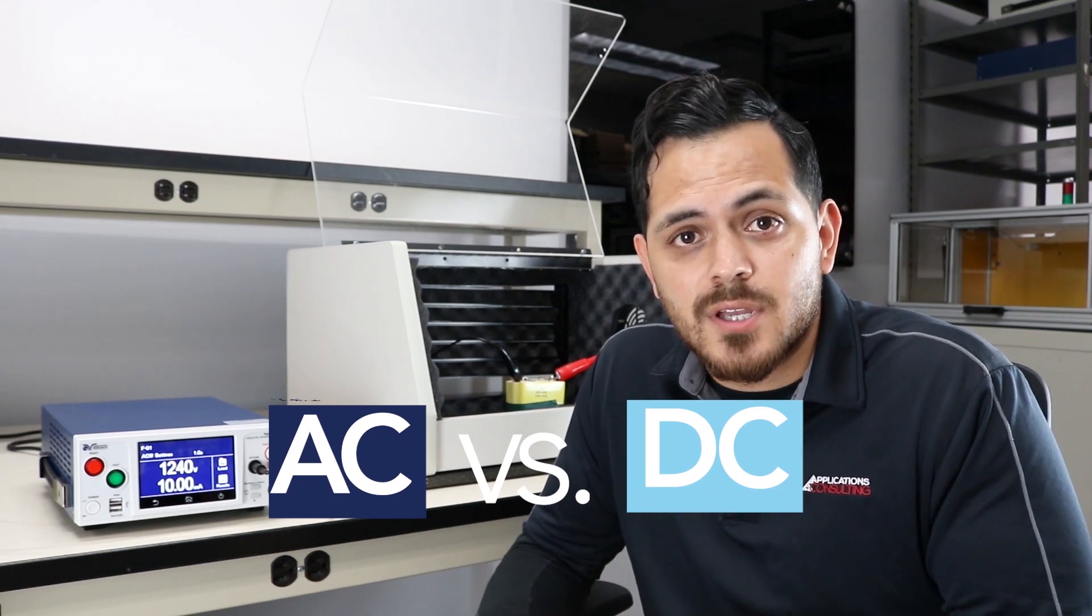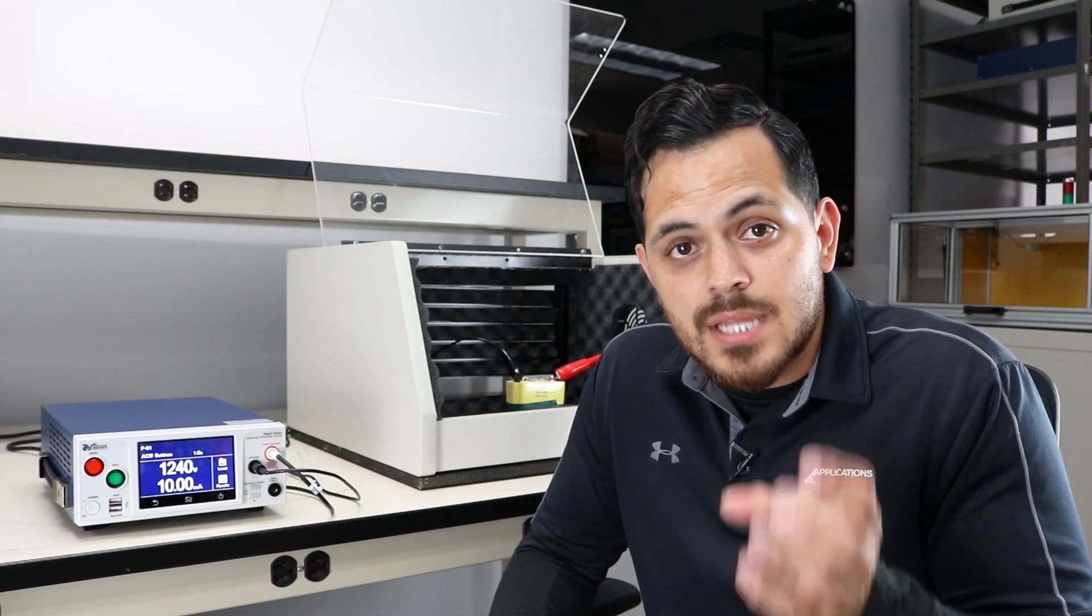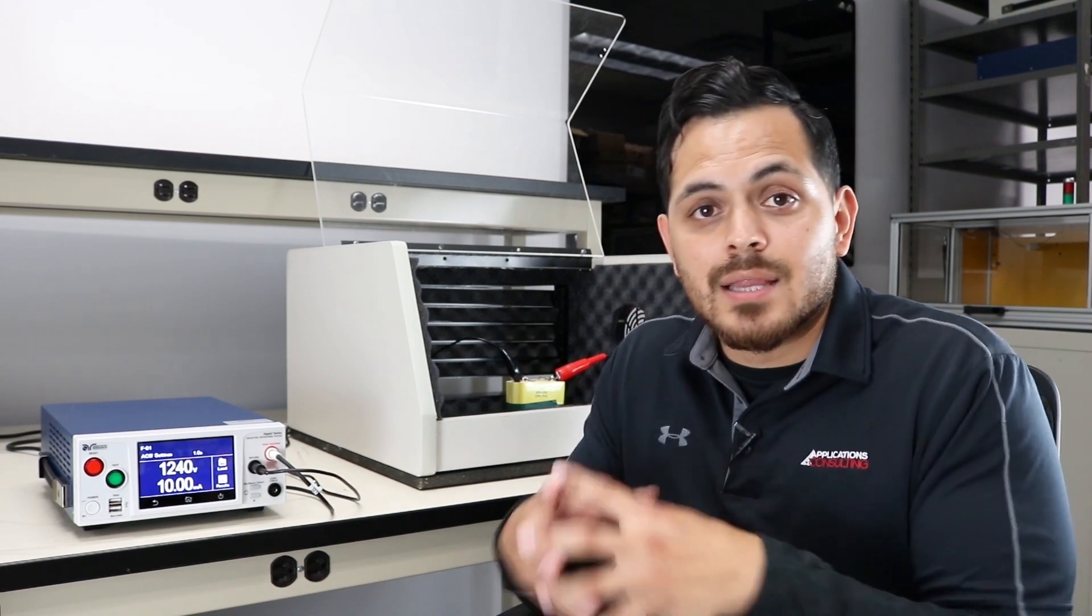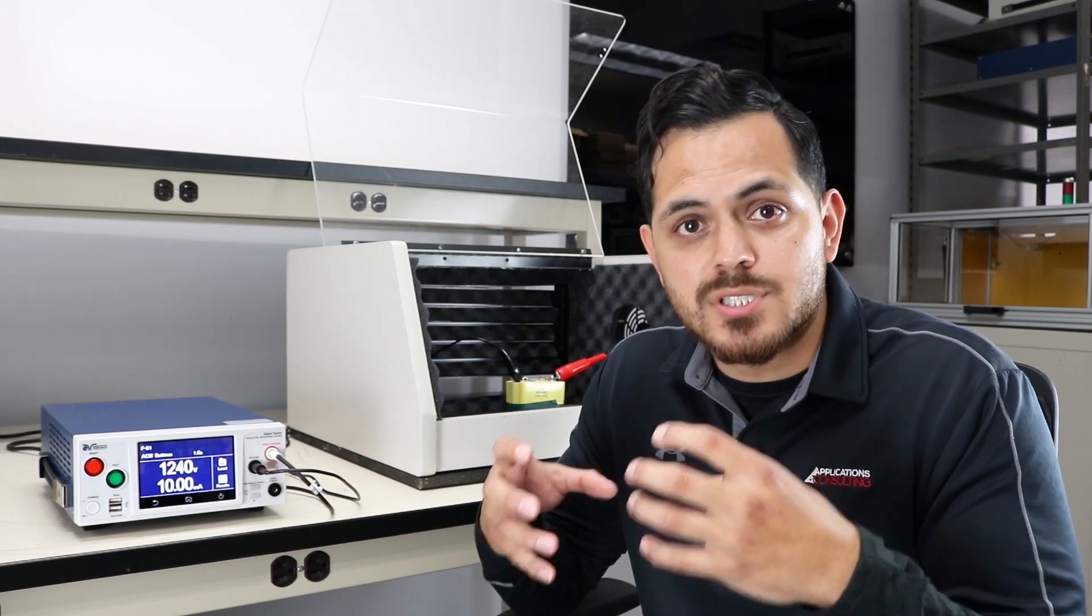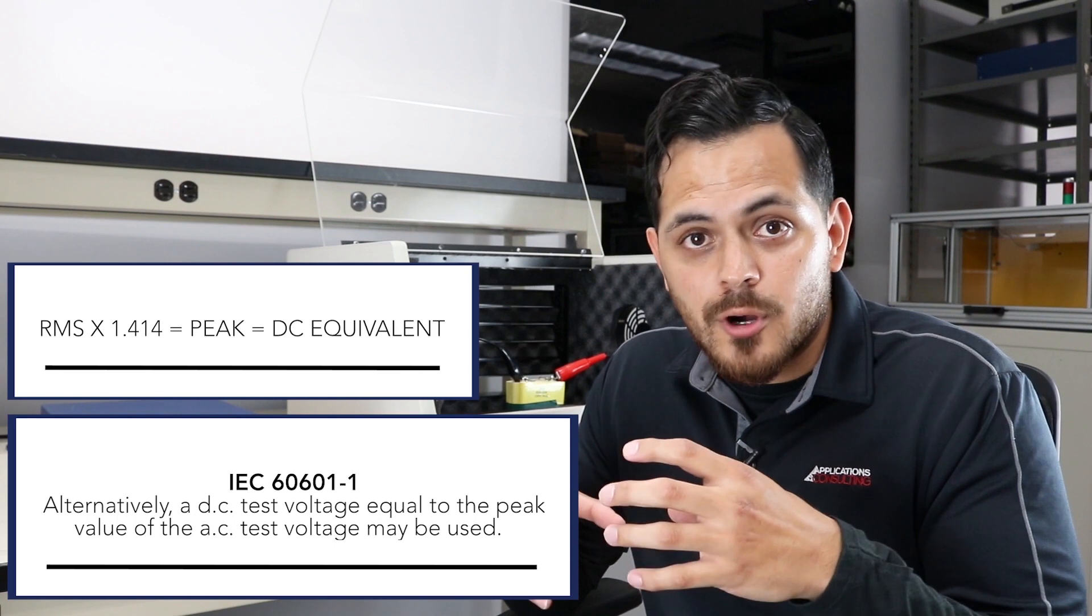Before we begin contrasting AC versus DC, you want to confirm that the standard you're adhering to gives you the option to test in DC. A lot of the standards that our customers are testing to have specific language that says alternatively a DC test may be performed at the equivalent AC peak voltage.